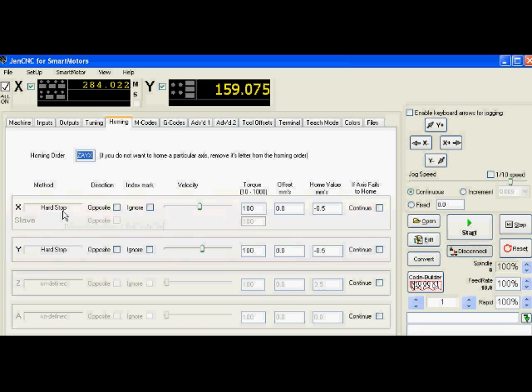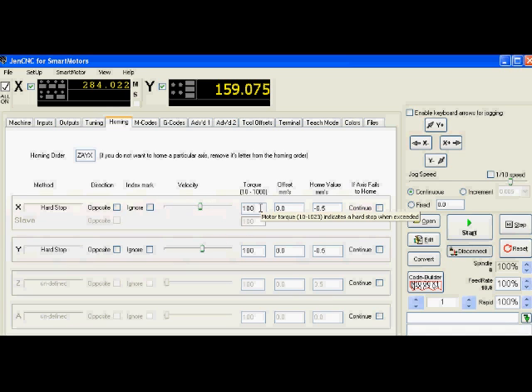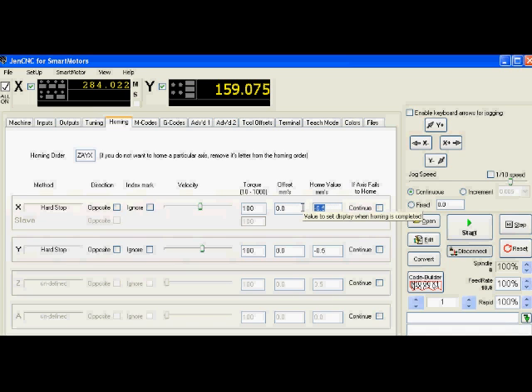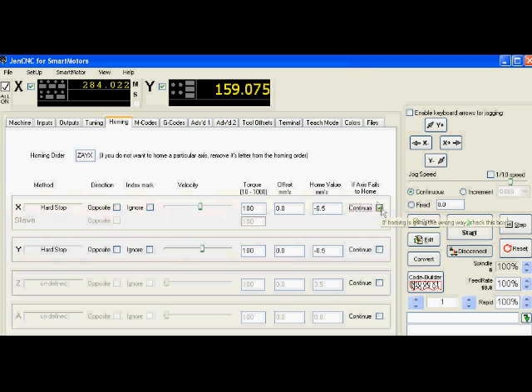First you see X axis is set up homing method home to hard stop. I've got a different velocity which I can toggle back and forth. I have a torque value I can set from 10 to 1,000. That's just a force value. 1,000 is pretty much full torque out of that motor. You do not want to set it to 1,000. That is very risky unless you have a high torque application to turn against, but most likely you will not set it that high. You have an offset in terms of millimeters and you have a home value. When you hit home, what do you want to call that value? And if you want, you can select here and continue if that axis fails to home. I am not going to do that. If one of my axes fails due to homing, I want to know about it and fix whatever mechanics may be at fault or whatever setting in the software may be causing that.